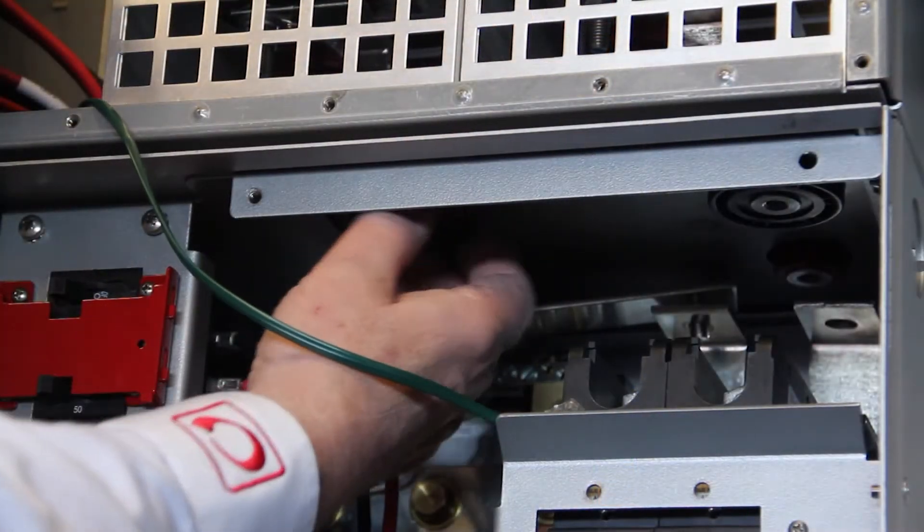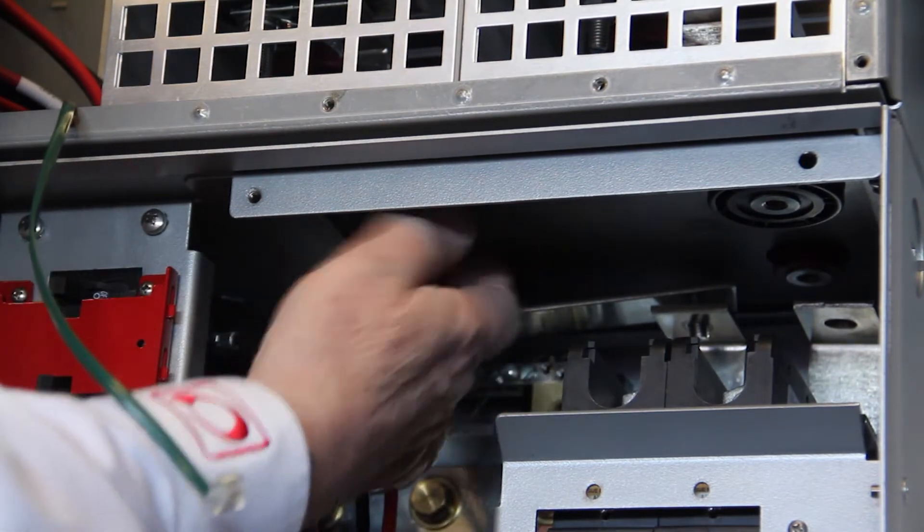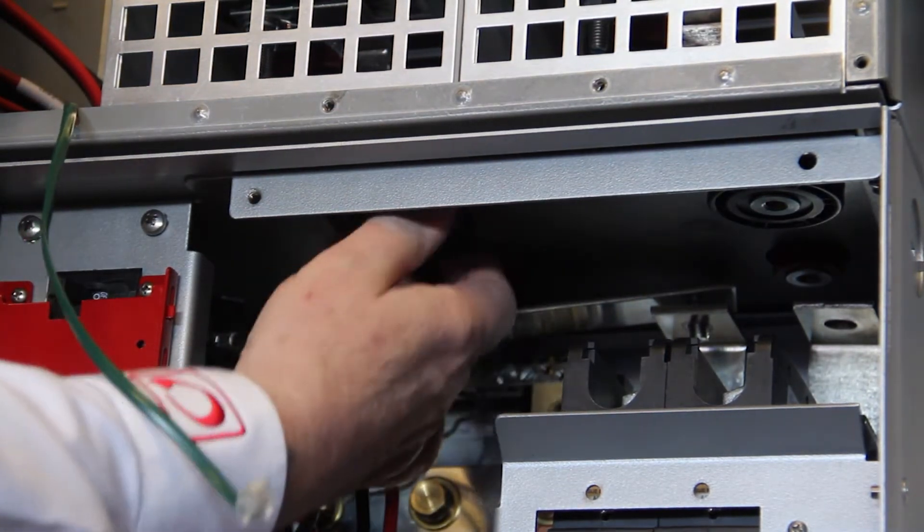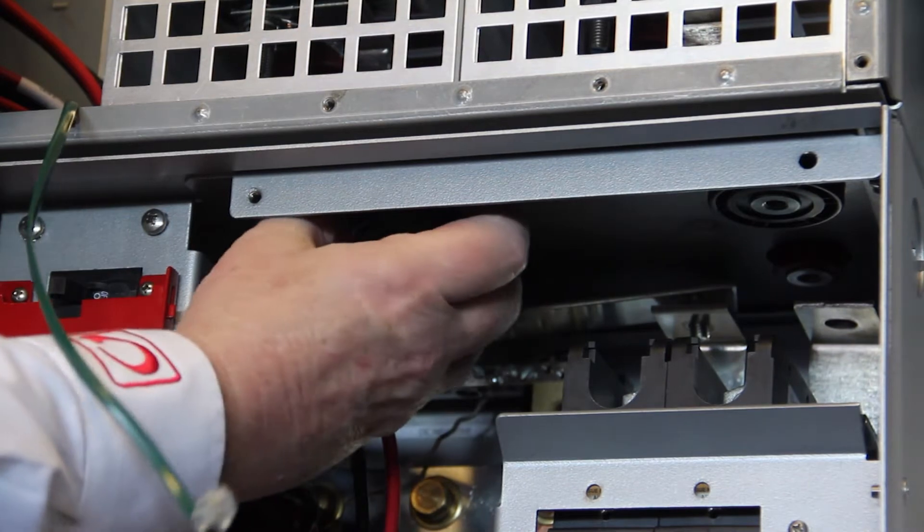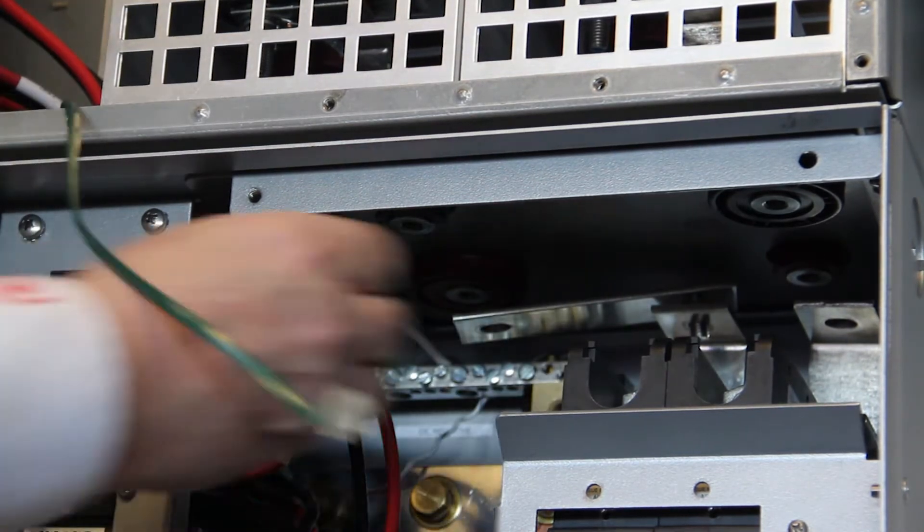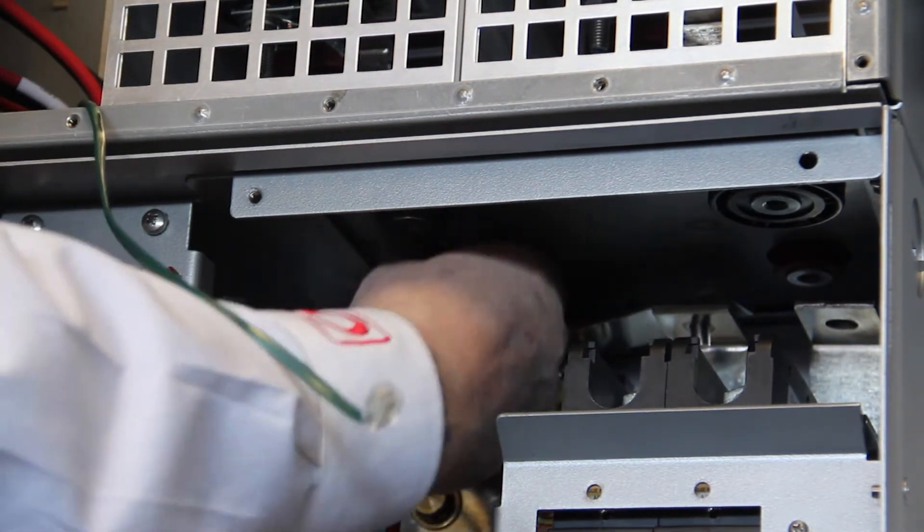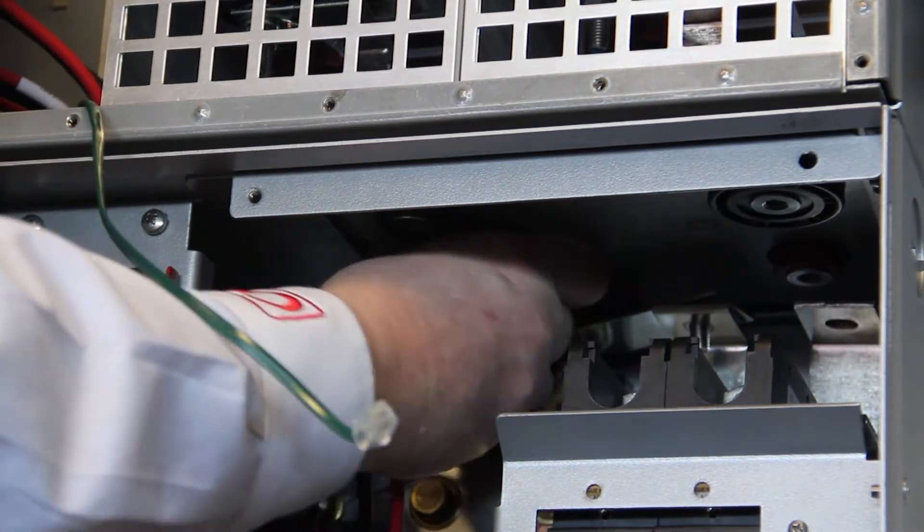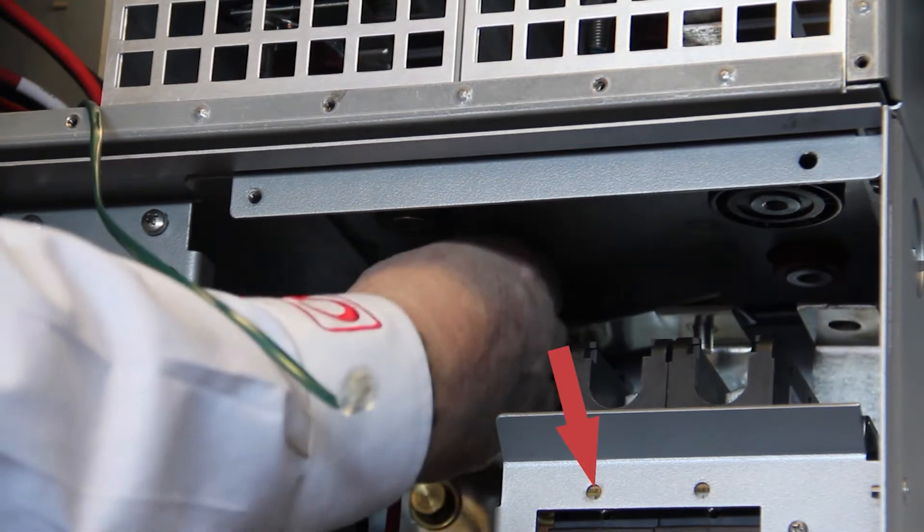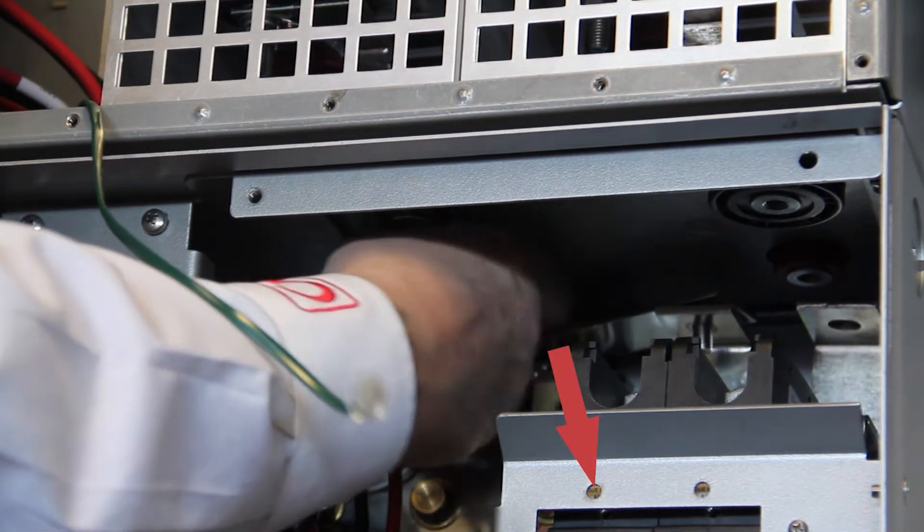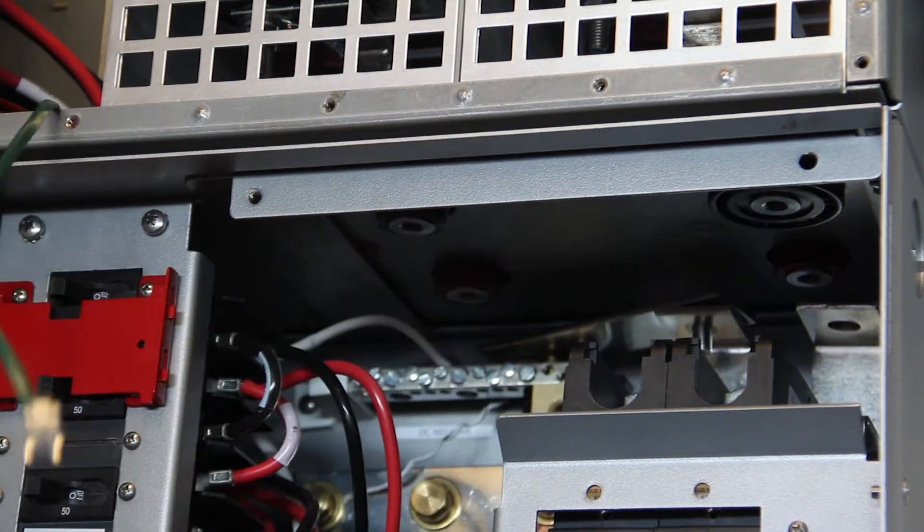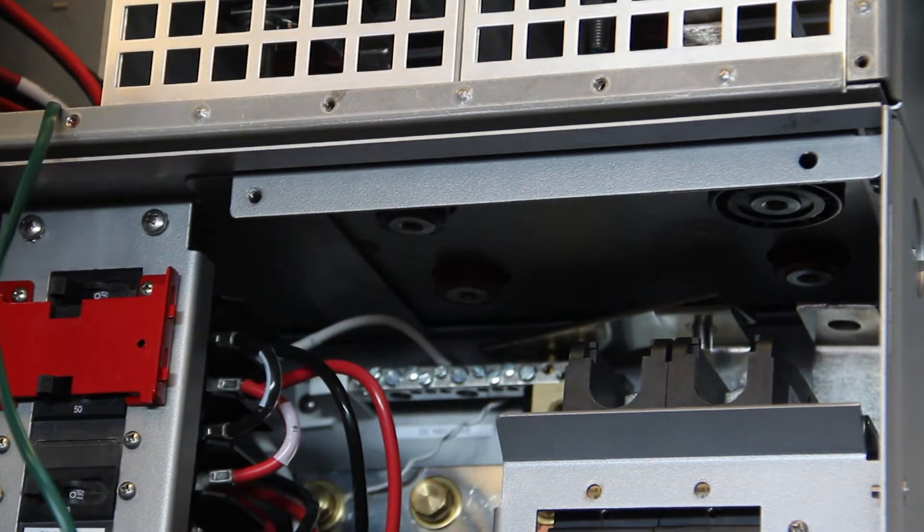Remove the battery terminal nuts by turning them counter-clockwise, which secure the power module to the chassis. It may be necessary to pry them with a screwdriver. Remove the four Phillips screws that hold the two 175A DC breakers to leave space for the far right nut to be removed.